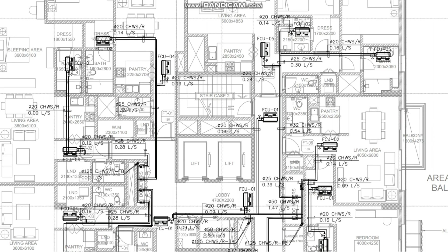For the underground line, I have taken it above like this, and it is very good engineering practice - you must always take the line above. If you take the line below, there is a chance that dust and dirt particles will settle down at the bottom. So it is always recommended to take the branch from the top. This applies to the underground line, and when it comes to the building side as well, you should always try to take the takeoff from the top side, not from the bottom side of the connection.